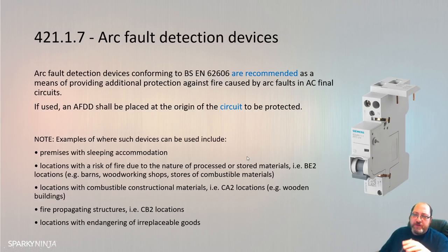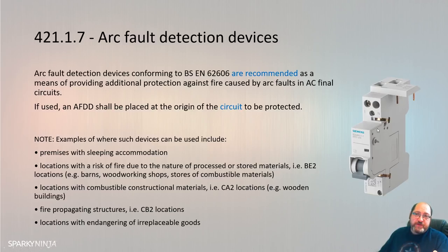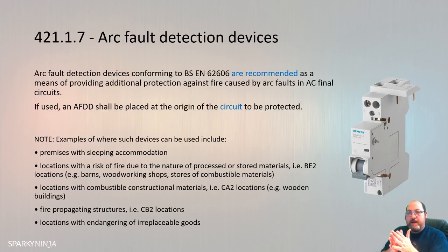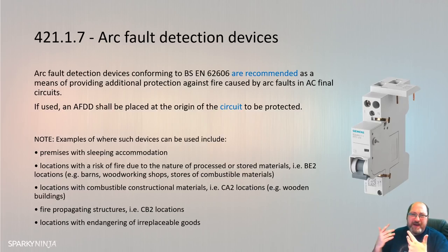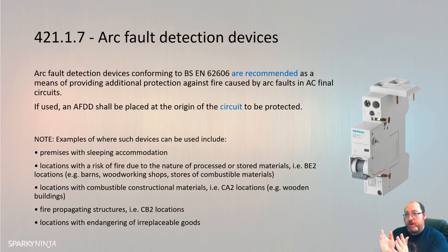AFDDs are considered a device that goes beyond current MCBs and RCDs. MCBs work on overcurrent and overload protection; RCDs work on imbalance of current to earth. AFDDs monitor the waveform and identify distortions that indicate arcing events. They work with parallel arcs — an arc between one conductor to another within a single flex, such as line to earth or line to neutral — but they'll also work with series arcs, which are dictated by the load because you need power flowing to create them.